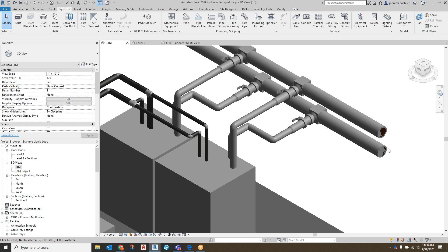Certainly, very fair point. On that note, it's worth considering that some of the users here are going to be IT managers, IT owners of these buildings, not necessarily mechanical or electrical engineers. There are considerations that someone with experience would know. One I always bring up is insulation - if this is cooling water that's below the dew point, we're going to have condensation. So most loops you'll see that are chilled water, in the traditional sense, will be below dew point on the supply end and will condense, so they need to be insulated. End users might not be aware of this.